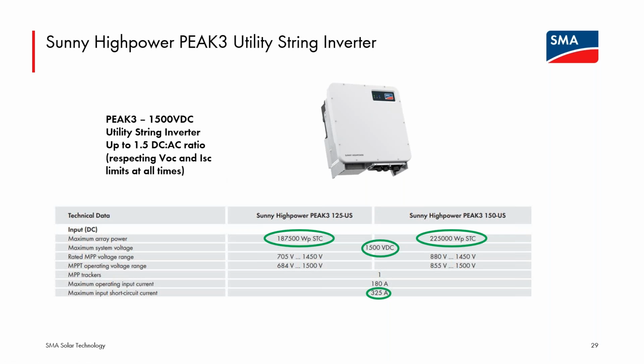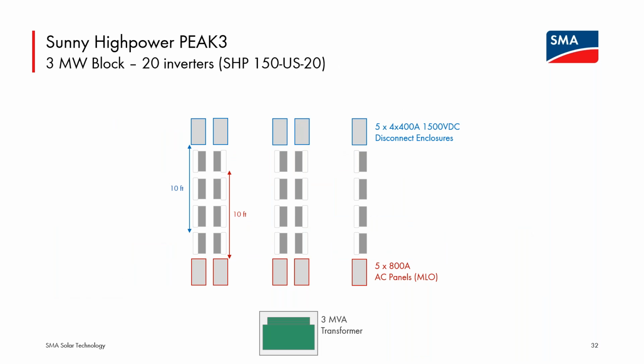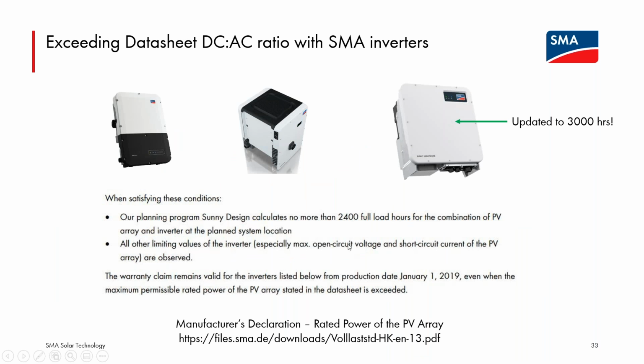We would want you to do a design for the specific site you're considering, with all of the correct design factors, run the design, and look at those peak load hours or full load hours, the full load hours for that specific design. And we've just upped the limit for the PEAK3 to be 3,000 full load hours. So again, if you wish to exceed that datasheet 1.5 DC to AC ratio, that's what you would need to do, either with SMA's help or on your own.